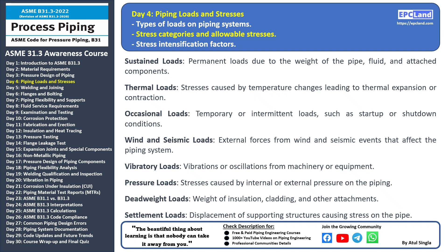Secondary stress occurs due to temperature-related changes. When the pipe expands or contracts because of temperature variations, it generates secondary stress. These stresses are usually transient and occur during start-up or shut-down. Occasional stress comes from temporary or intermittent loads — these are non-permanent conditions such as those experienced during system start-up, shut-down, or other irregular operations.